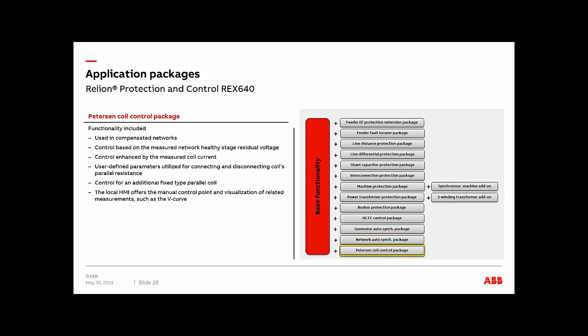And finally here, there's a Petersen coil control package that's available as well. This one is used in compensated networks that have, of course, a coil, and you're able to control it. So pretty much you can issue control of an additional fixed coil. If you wish, the relay can also switch on or off the resistor if you have that capability, the parallel resistance used in this coil. So this is merely a control function. It's available there. Through the local HMI, you're also able to see the V curve for the current. So you're able to see that as well locally on the relay.